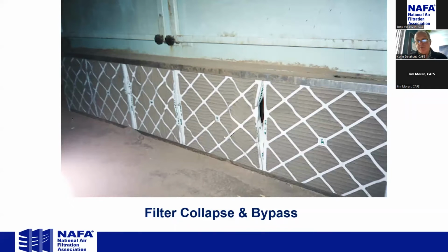Very common in areas with high moisture are pleated cardboard filters. Cardboard and water is not a very good combination. Once these products get wet, they never regain their tensile strength or their structure, and they start to collapse, leaving substantial bypass and chances for the filter to rupture. And again, you can see a very large hole here, very large particulate, bugs, atmospheric or contaminant just bypassing the filter and entering the system. There's going to be a coil behind that, and I think if you looked at that coil, you would see staining downstream of this gap, and also dirt on the floor and that type of thing.